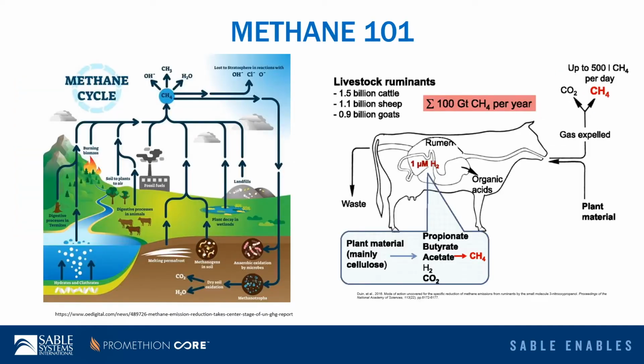So anyone measuring methane, or CH4, should know a few basic things about this gas. First, despite the rumors on the street, methane is actually an odorless gas. It's a trace component in our atmosphere, and it occurs at levels of about 1.9 parts per million, depending on the time of the day or the season or where you are geographically.